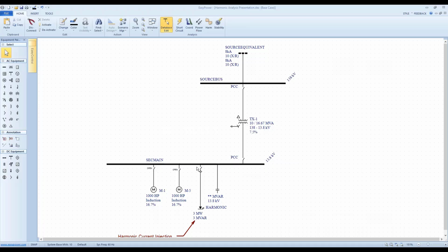Well, I will go back to that. The procedure should be to monitor at the service entrance. If there's multiple service entrances, then you need to monitor at each of those service entrances. You should do your analysis with the appropriate IEC instrument for a 1 week period, taking measurements so you get the statistical analysis that's required by the new standards, and do that at each main service entrance area. But while doing that measurement, the capacitors must be offline.